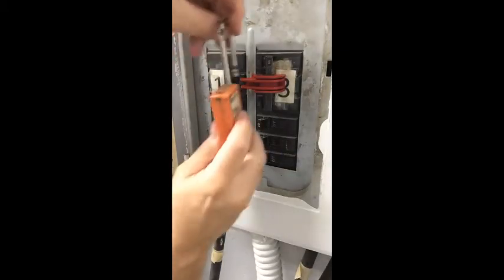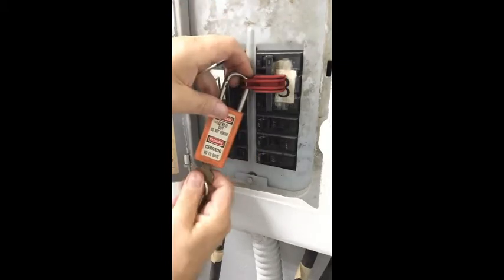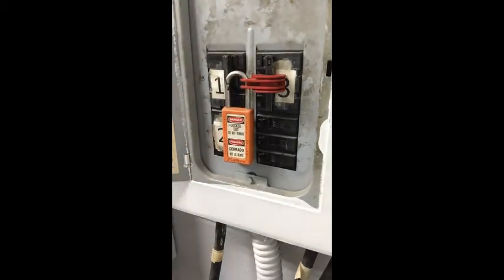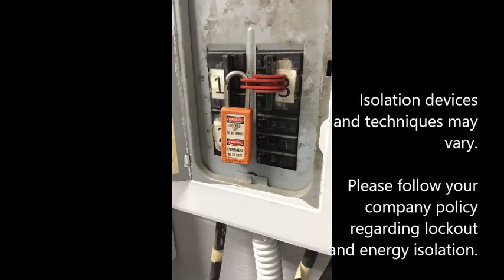Okay, then I'm going to go ahead and put a padlock on there that says it's locked out. I'm in control now with the power. When I'm done, I'll take it back off. But in the meantime, I'm going to leave this on while we discuss some of the electrical things that have to do with this fryer. And I have the key. So as long as I have the key, I have control. And we just want you to be safe. You should do the same thing. However you guys are set up, I don't know what kind of lockout tagout devices you have. This one works rather well on most breakers.